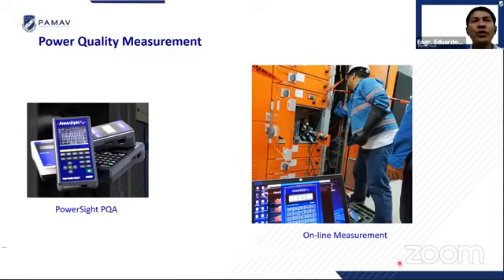So how do you install a power quality measurement in the field? First, you need to have safety, because if you don't, maybe you will be electrocuted. So here we have gloves. Usually the rating is up to 1 kV for low voltage, and most of the power quality we measure is at the low voltage side. But sometimes they ask me, how can we measure power quality in the high voltage or medium voltage? We can measure through the current transformer and the voltage transformer.